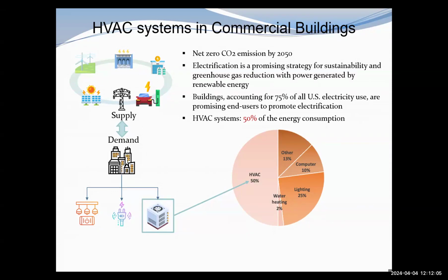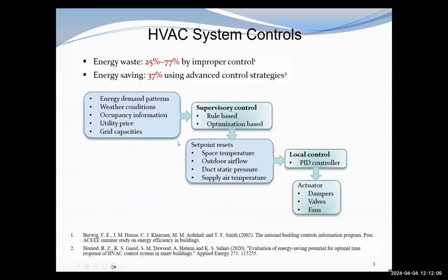That means we can do a lot of work on the HVAC system to achieve this goal. The HVAC systems include the supervisory control and the local control. As for the supervisory control, based on the energy demand patterns of the buildings, the weather conditions, occupancy information, utility pricing fluctuation, and the grid capacities, the supervisory control will dynamically reset the set points for our space temperature, outdoor airflow, duct static pressure, supply air temperature, etc., by using rule-based or optimization-based control strategies. And these set points will be the reference input to the local control loop.